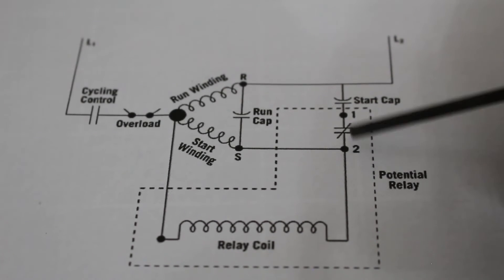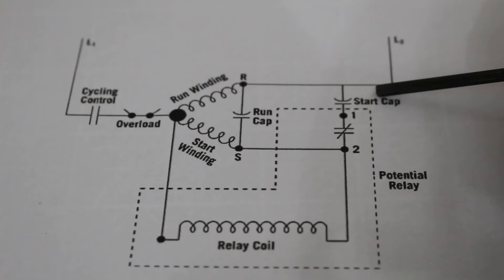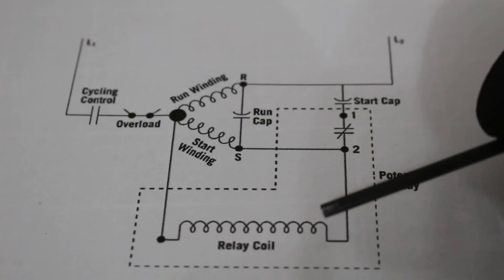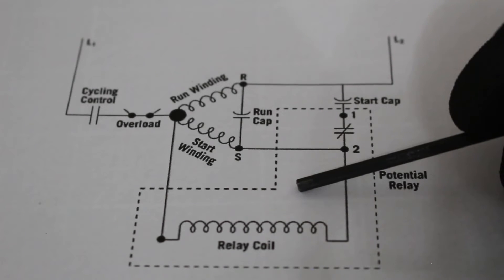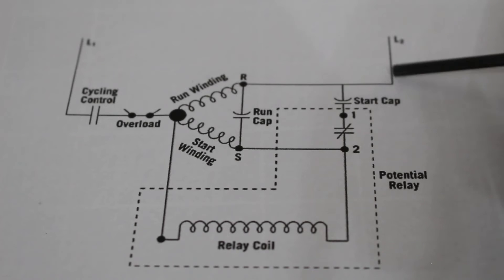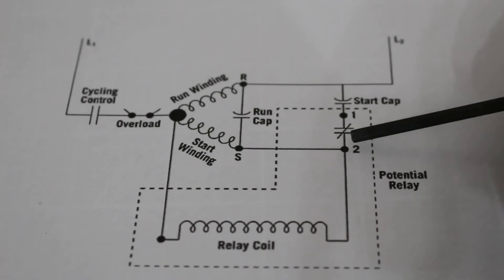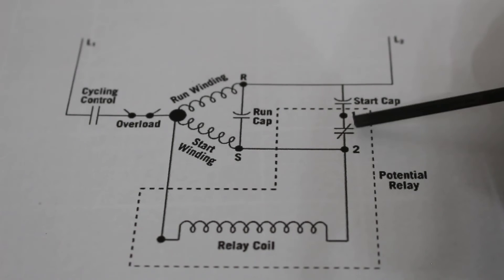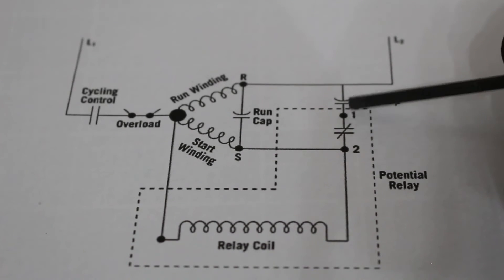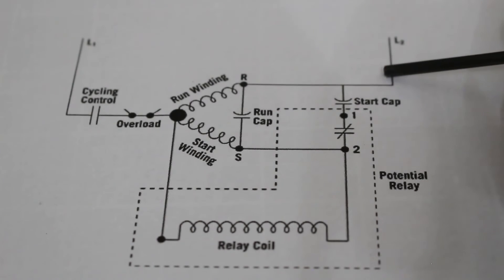What happens is that once your compressor is up to speed, we want to get rid of the start cap. And how that happens is something called a back EMF. EMF stands for electromotive force. So, each relay is calibrated to a specific EMF. So, what happens is that once the compressor is up to speed, that EMF is going to travel back and it's actually going to open the set of contacts. And once the set of contacts is open, there's no more flow to the start cap. So, now your system is just constantly running through your run cap and the system runs.